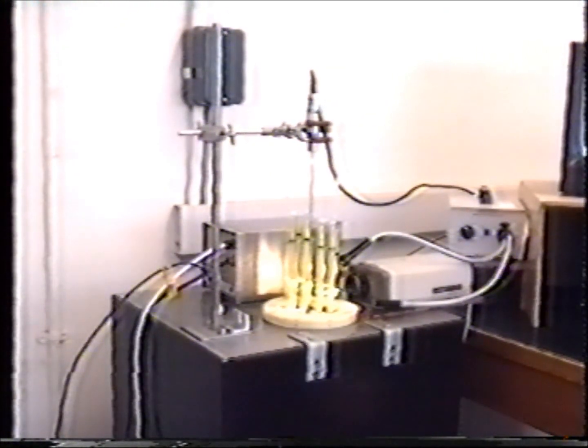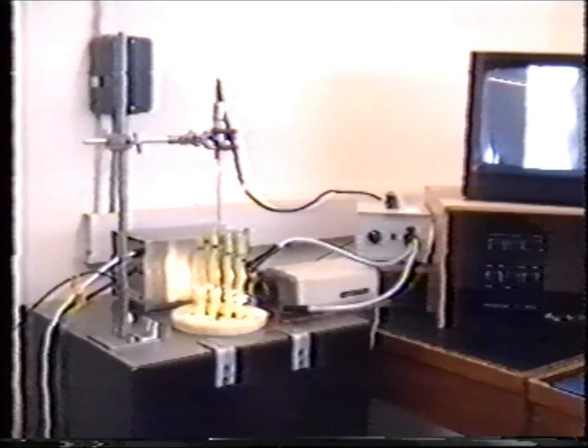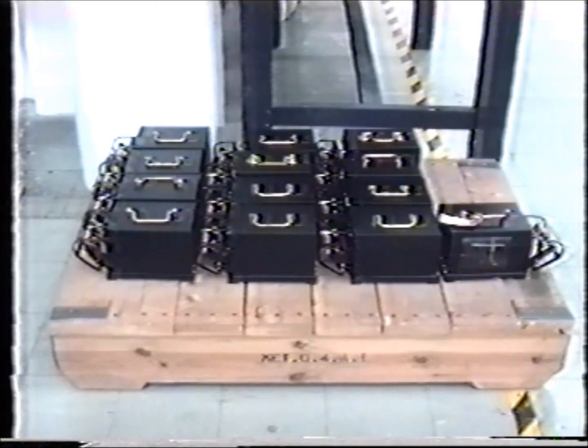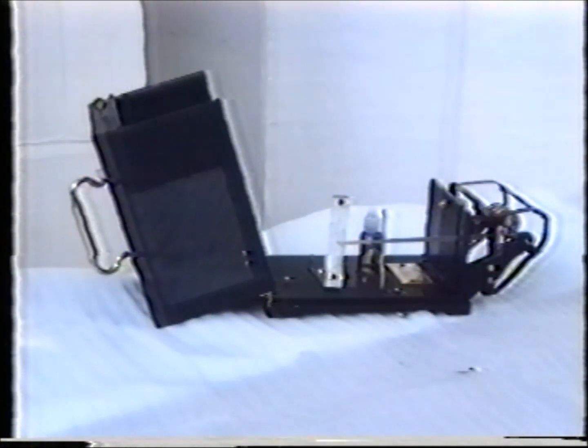The video system replaced a previous single microscope affair that caused staff a great deal of eye discomfort in previous years. Traditional autographic records are still a Met Office requirement, and so large numbers of thermographs are currently rebuilt by commercial companies and then calibrated in the laboratory. Many of these instruments are over 40 years old, but with regular refurbishment, their original accuracy can be maintained. They are of rugged construction and capable of recording to within half a degree Celsius, and are particularly useful in timing the night minimum temperature.